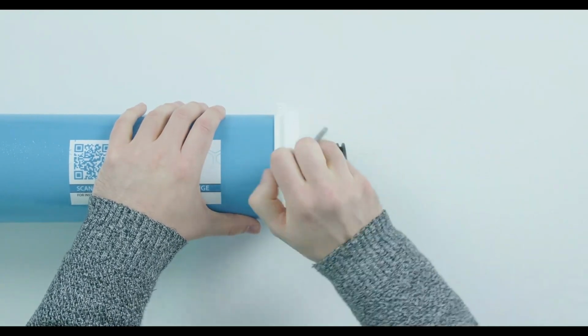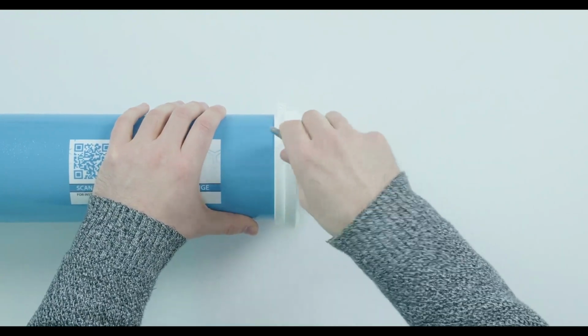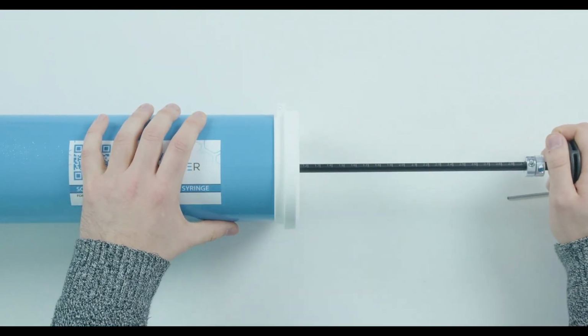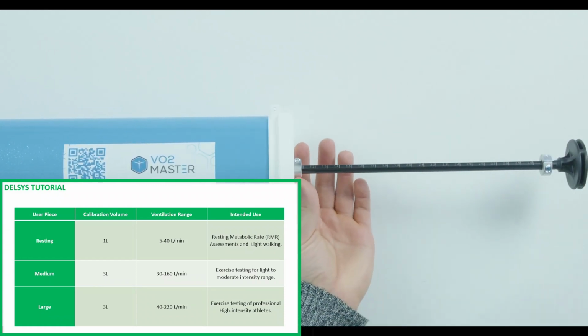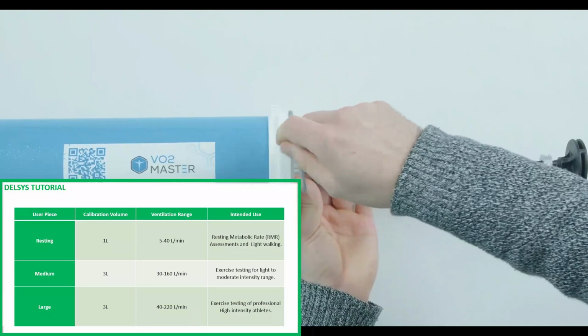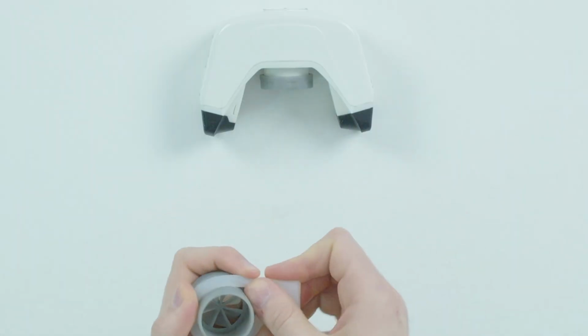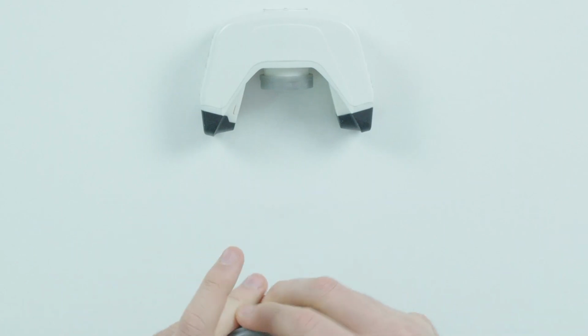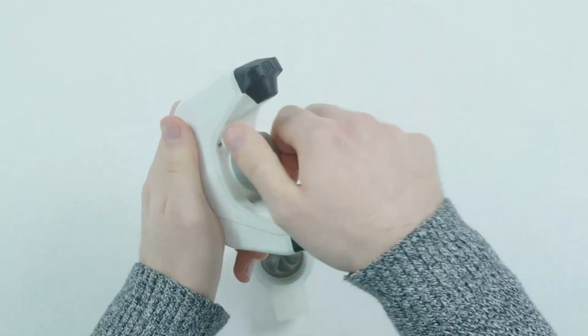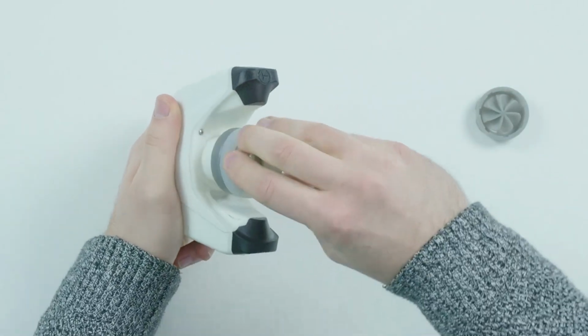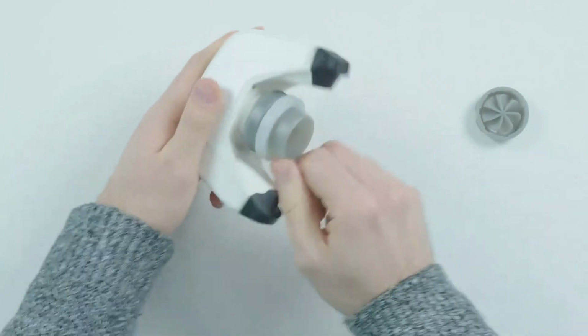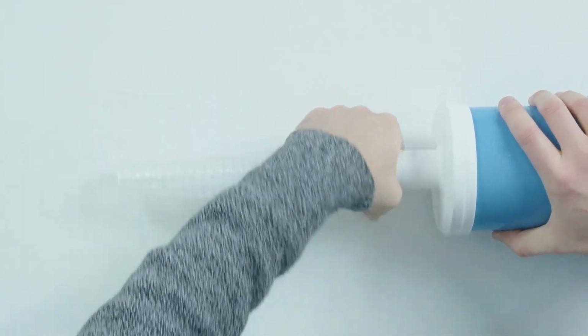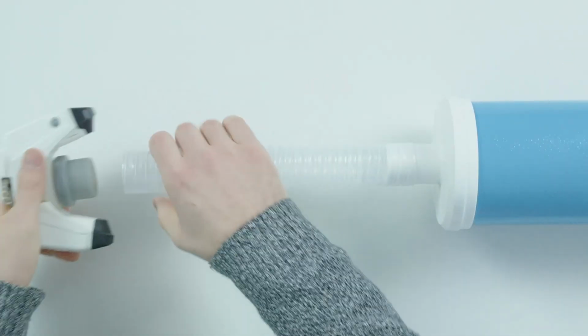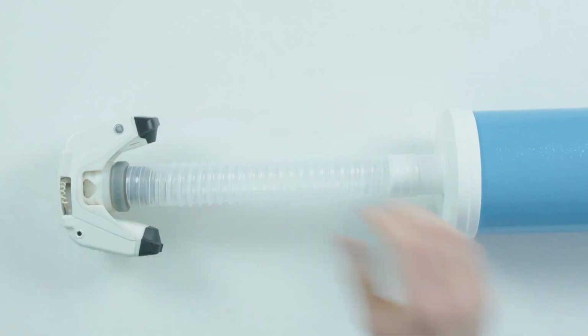Set the calibration syringe to your desired calibration volume by using the provided Allen key. This may vary depending on which user piece you are using. For more information, please go to the VO2 Master Product Manual. Place the silicone seal around the user piece and attach the calibration syringe adapter. Connect the VO2 Master Analyzer with the calibration syringe and the 30-centimeter flexible tube.